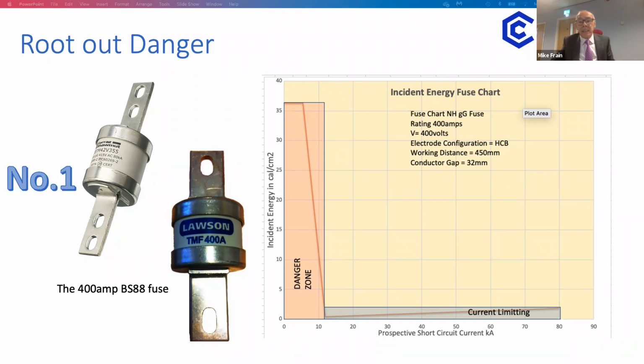On the right is an incident energy chart, which shows arc flash severity against prospective short circuit current for that same fuse. For horizontal conductors, which I mentioned earlier, the conductor configuration, in an enclosure, and I've highlighted the fast acting zone of the fuse. However, at faults below 12,000 amps, as you can see there, that's when the severity can escalate very quickly. And you can see that I've capped it off there at a 2-second disconnection time, and it's over 35 calories per square centimetre. So what does that look like?